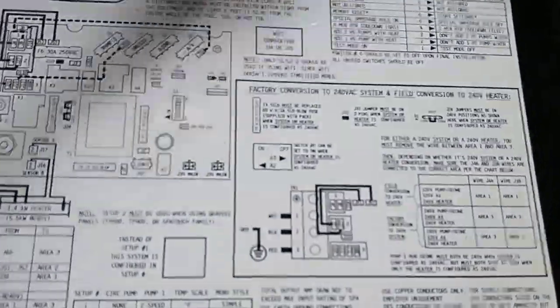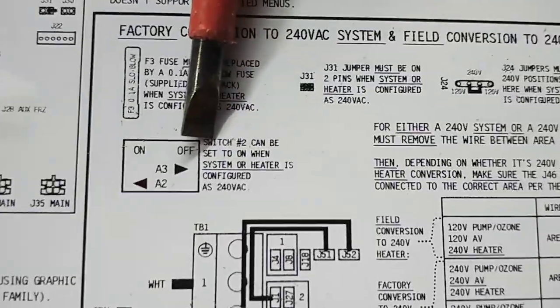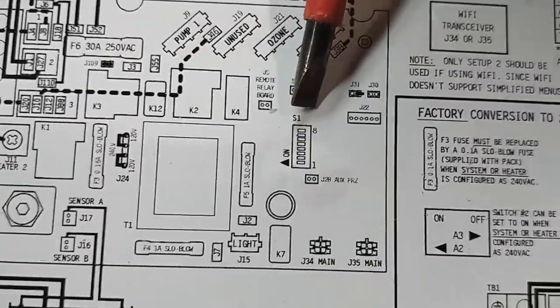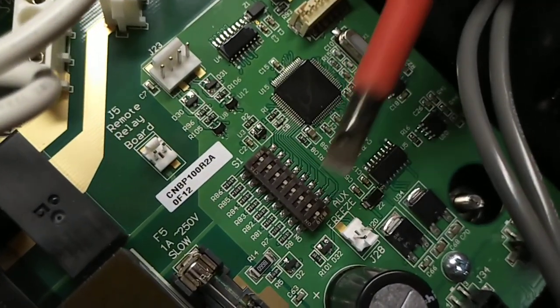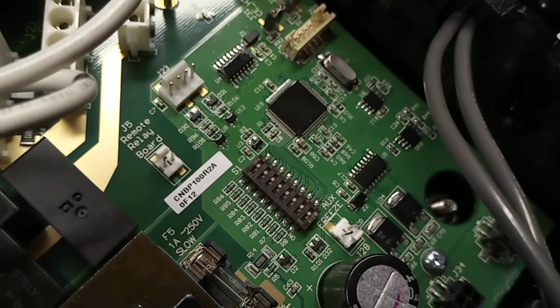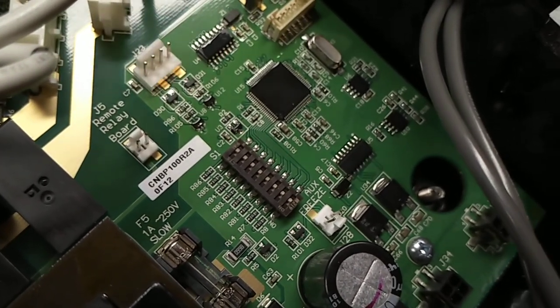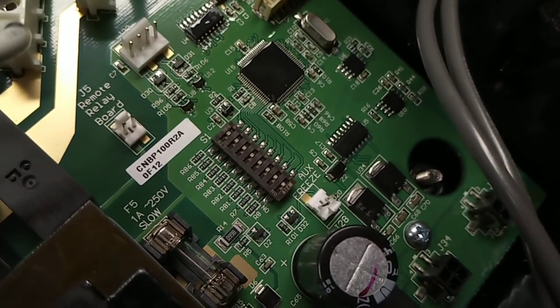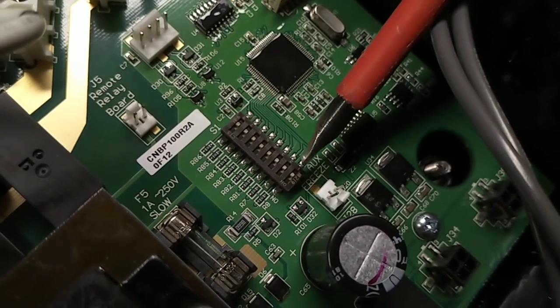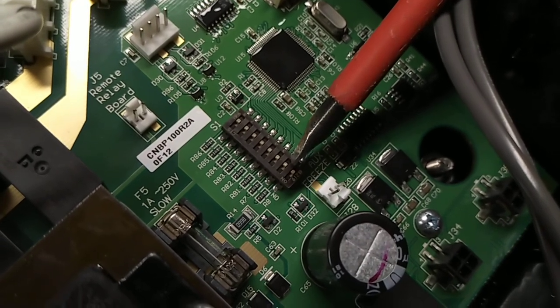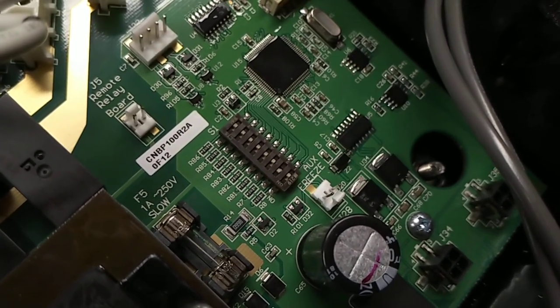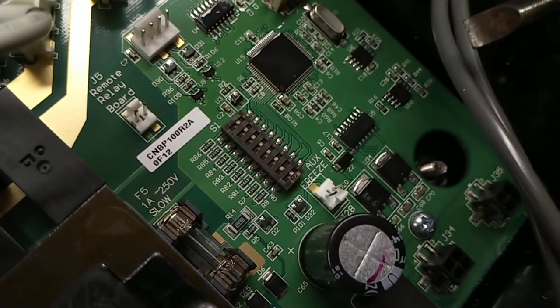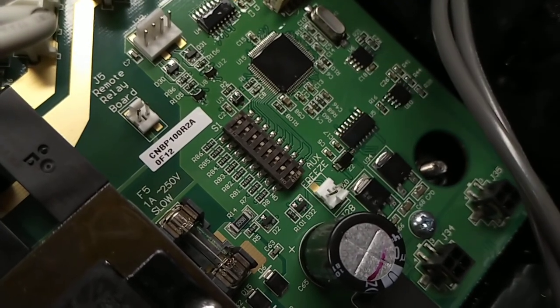Next step, we're almost there, is to look at the dip switch bank. This dip switch bank, which is located right here on the board, has a whole pile of tiny little switches. These little switches, you need to adjust one of the switches in here to allow your high-speed pump and heater to operate at the same time. So as long as you're installing this on something that's 40 amps or higher, you can adjust this switch. It's going to be number two. So from the bottom up, you want to count one, two, and move the second pin to the left. So it's only the second pin, which is actually the second switch, which is actually going to be on. Everything else is going to be to the right or off.